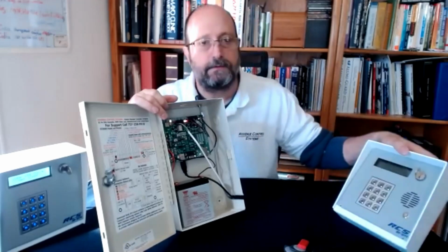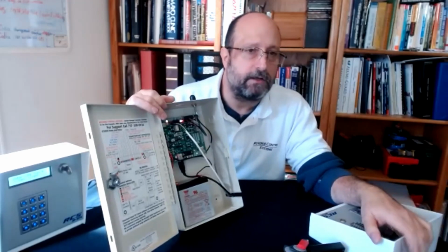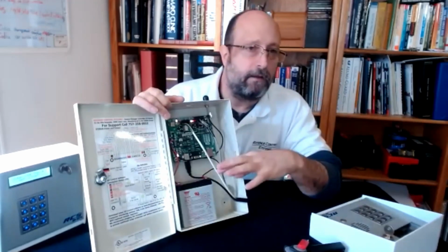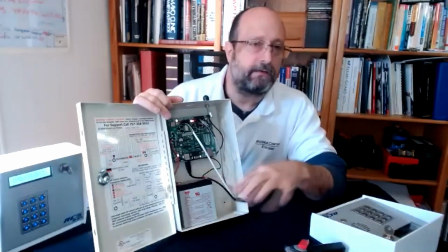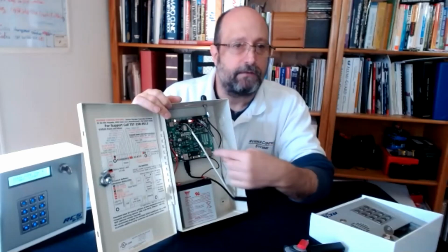The online system on site, we don't ship the keypads with the power supply either, but they do take 12 to 24 AC DC. You can pick it off the operator. Also, the system manager provides power for up to 5 keypads, optionally 10. We could boost the power supply to 10 keypads. So you could, with the option, power 10 keypads directly from the system manager.